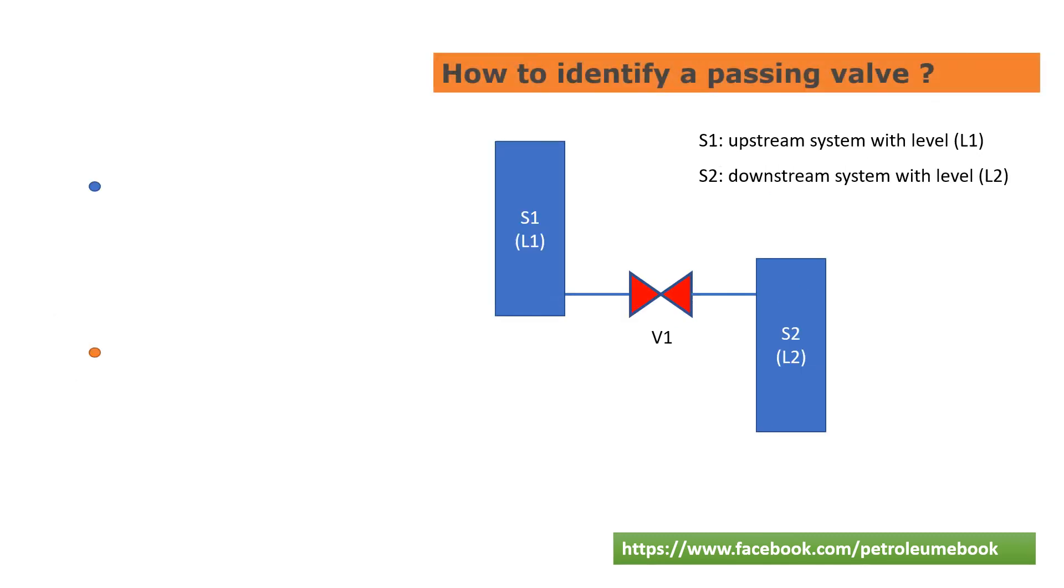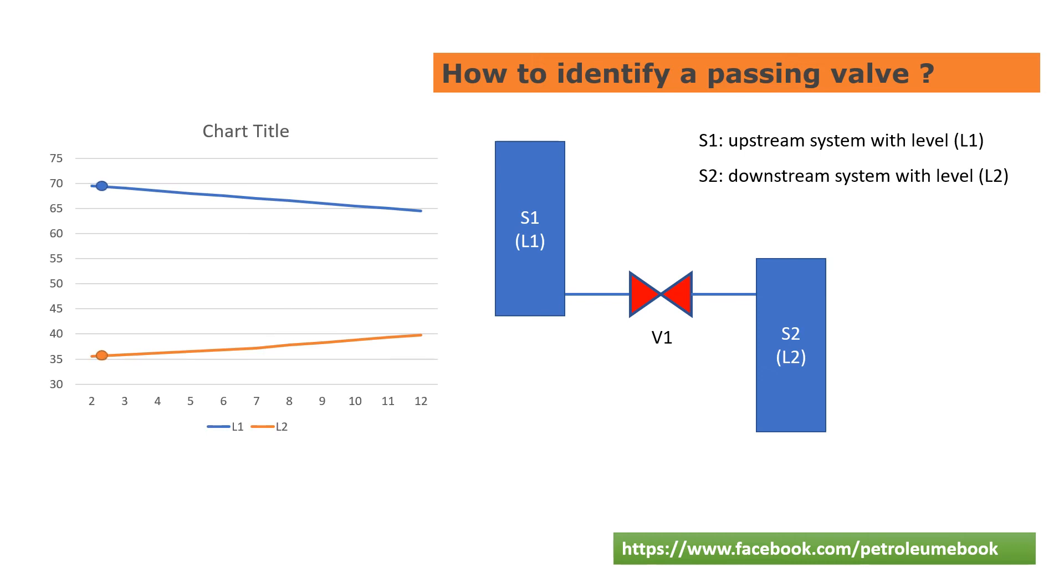The next example is with two isolated systems S1 and S2 with levels L1 and L2. After we fully close V1, if the level L1 still decreases and level L2 still increases, we can conclude that valve V1 is passing.